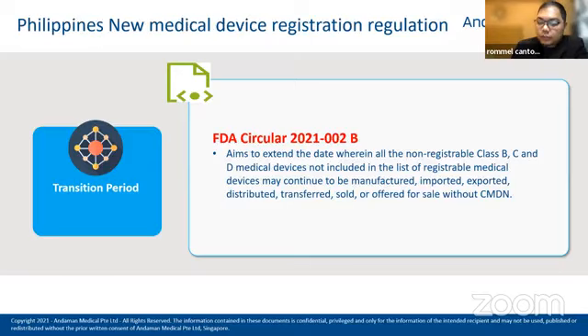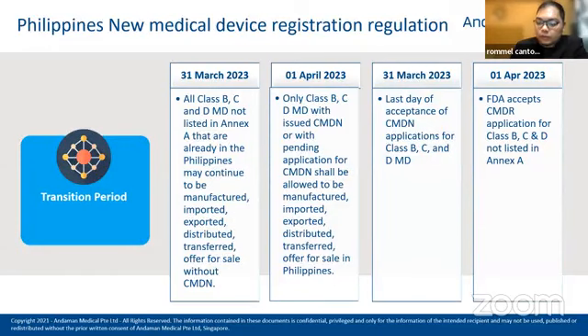On the next slide, you will see the periods of these transitions. So until March 31, 2023, next year, all Class B, C, and D medical devices not listed in Annex A that are already in the Philippines may continue to be manufactured, imported, exported, distributed, transferred, and offered for sale without a CMDN. But starting on April 1, 2023, only Class B, C, and D medical devices with issued CMDN or with pending application for CMDN shall be allowed to be manufactured, imported, exported, distributed, transferred, and offered for sale in the Philippines. A pending application is defined as an application with an issued order of payment or one that passed the FDA pre-assessment.